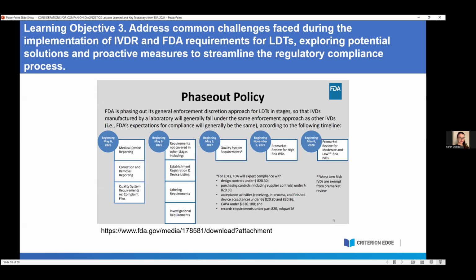As far as the timeline goes for pushing forward with our attempts to integrate these rules for LDTs, the beginning stage, stage one, is going to occur in May of 2025. That marks one year from the publication of the final rule. And that's where the FDA is going to start to expect compliance with medical device reporting requirements, correction and removal reporting requirements, and QS requirements that require your complaint files. And there are other requirements during this phase out policy as they're trying to implement these different requirements over the next few years.